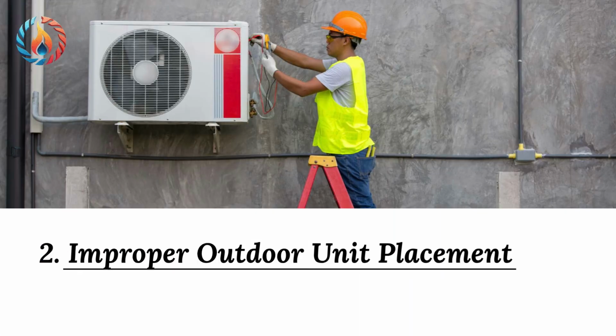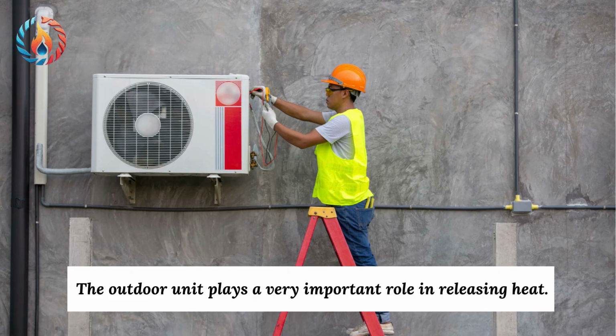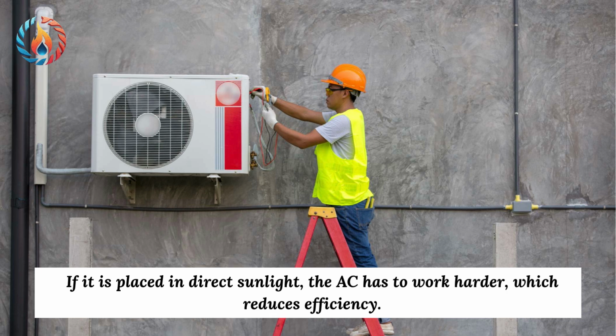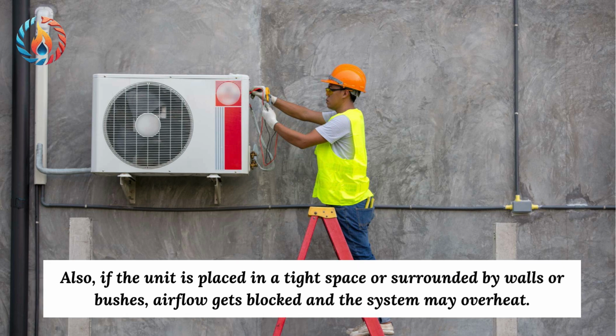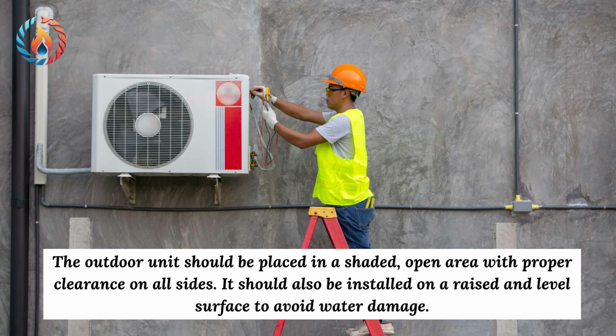2. Improper outdoor unit placement. The outdoor unit plays a very important role in releasing heat. If it is placed in direct sunlight, the AC has to work harder, which reduces efficiency. Also, if the unit is placed in a tight space or surrounded by walls or bushes, airflow gets blocked, and the system may overheat. The outdoor unit should be placed in a shaded, open area with proper clearance on all sides. It should also be installed on a raised and level surface to avoid water damage.